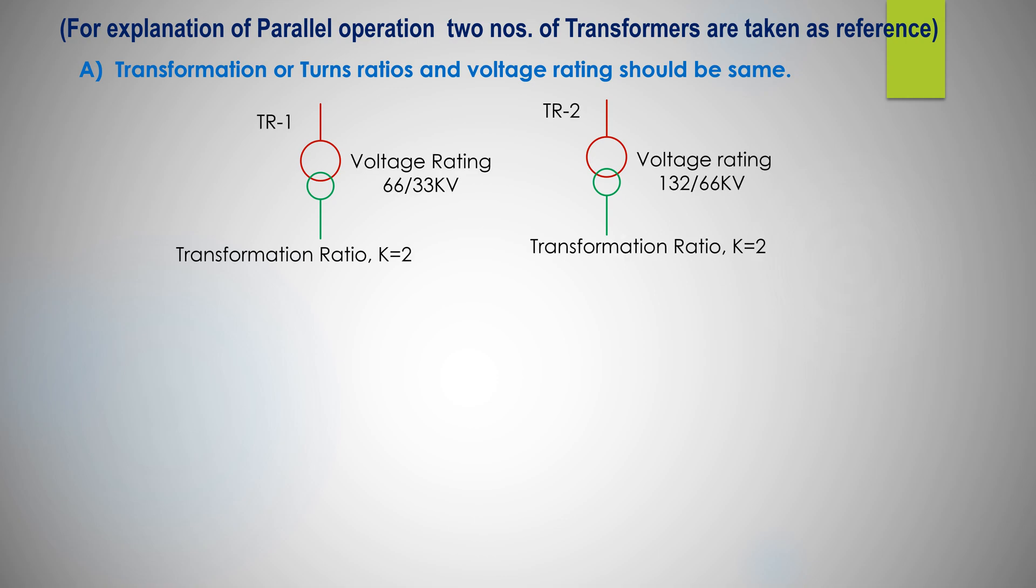As example, a transformer of voltage rating 66/33 kV of transformation ratio 2, another transformer 132/66 kV of transformation ratio also 2. So the transformer should not be parallel as their voltage ratings are different: one of 66/33 kV and another of 132/66 kV.